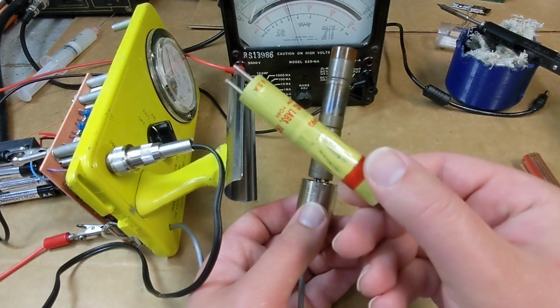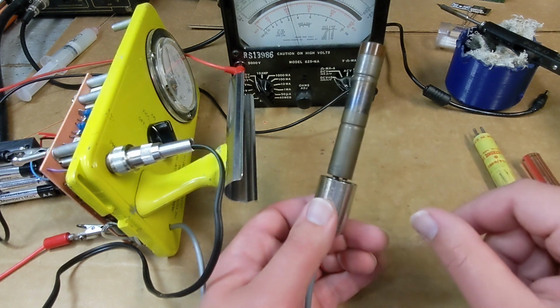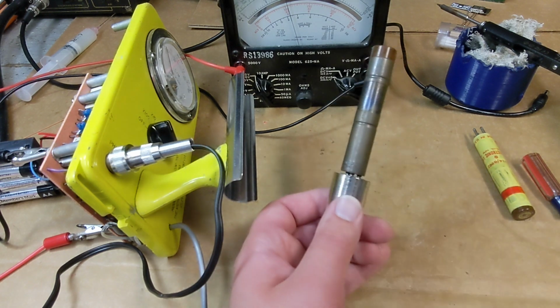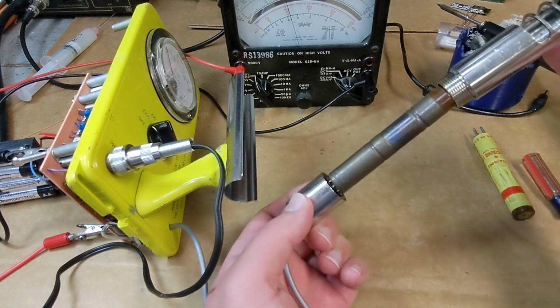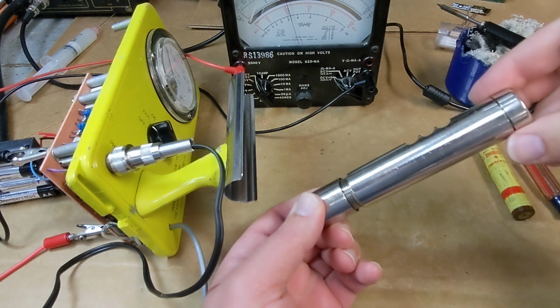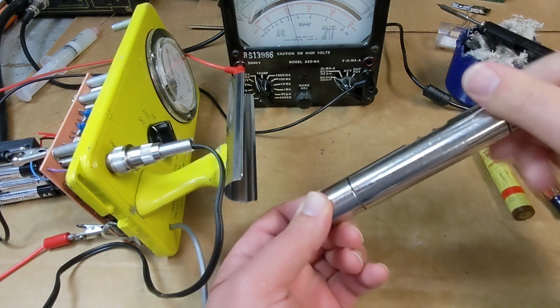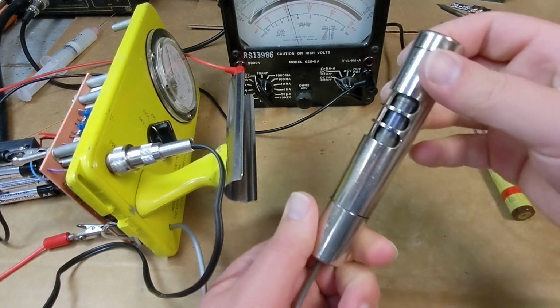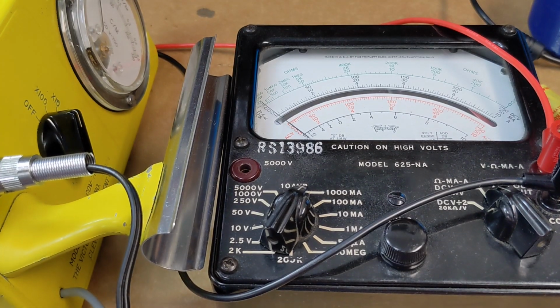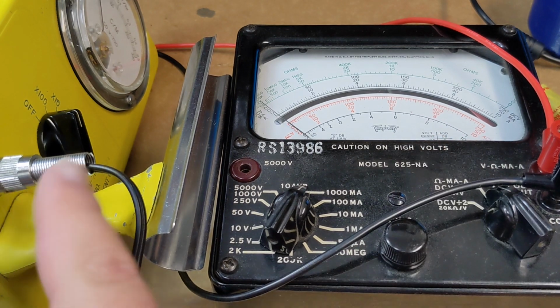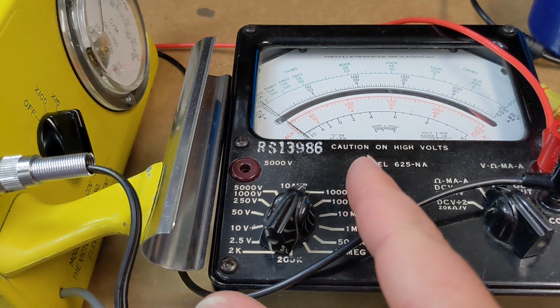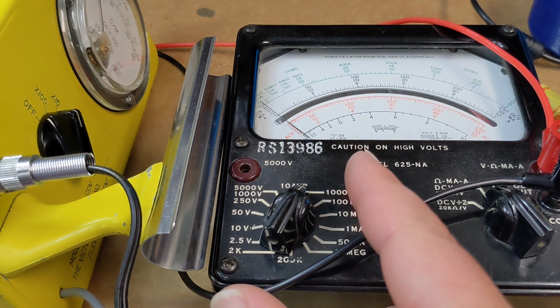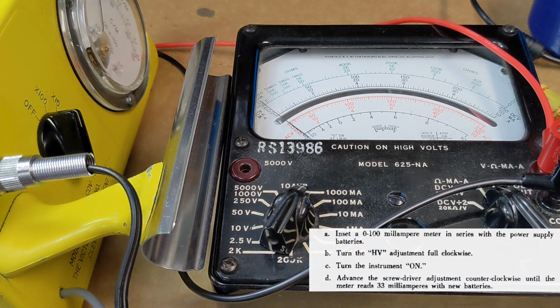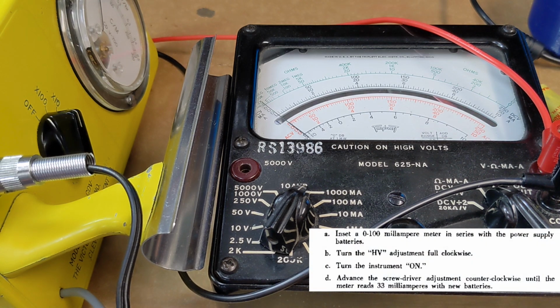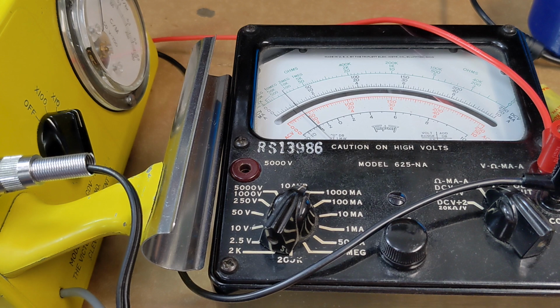I believe this plastic sleeve is meant to be kept in place. So that means I can put this back on. Now another thing is that if it's working correctly, the power draw of this should be 33 milliamps. The manual doesn't say where you put the amp meter in series. I just put it in front of the positive terminal, the red wire, and I get something more like 100 milliamps.